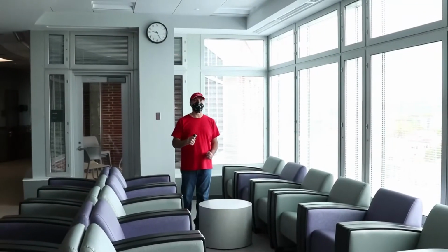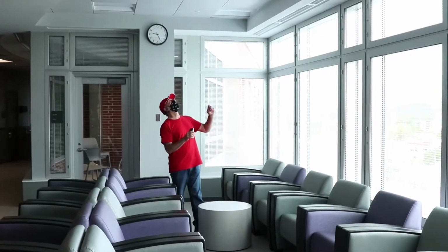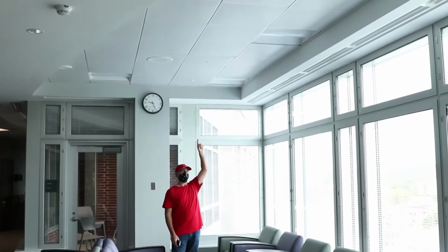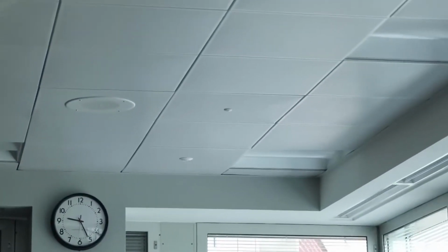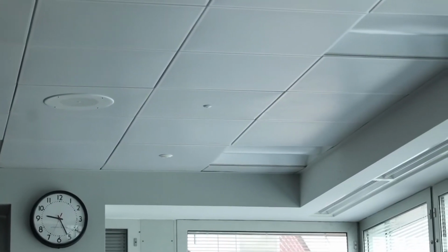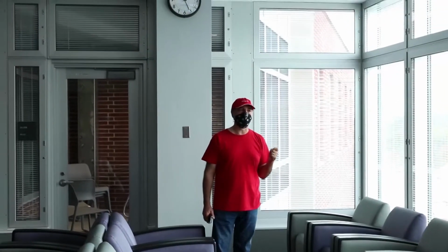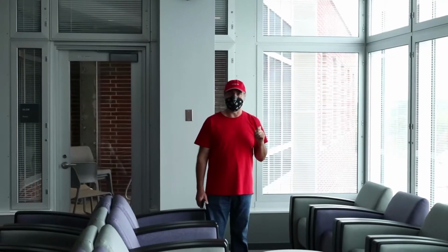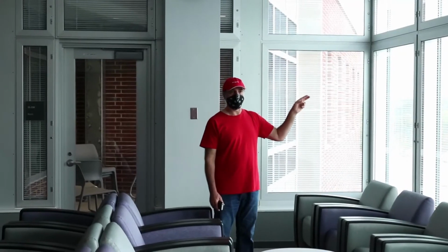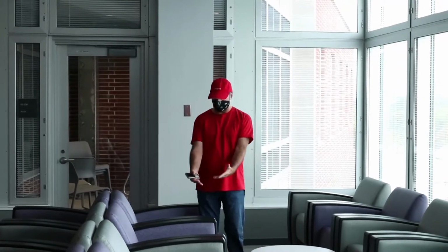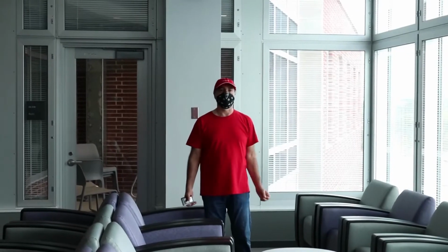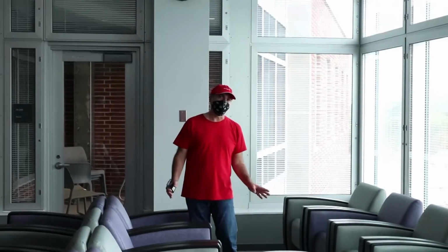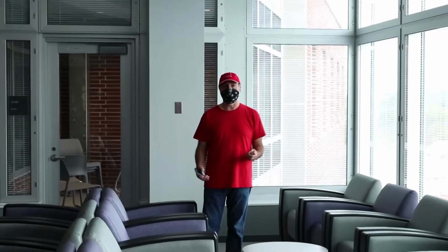And that's because these lights not only respond to that switch, but there's a daylight sensor right here. What that daylight sensor does is take into account the amount of light coming through the windows and dims these lights accordingly. So right now, the day we happen to be doing this, it's too bright for these lights to turn on. So that's why the lights are off, even though I've raised them to full. The daylight sensor overrides that and says there's enough light in this room, and that's why these lights are not on.